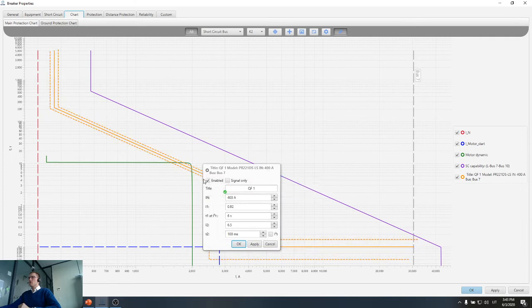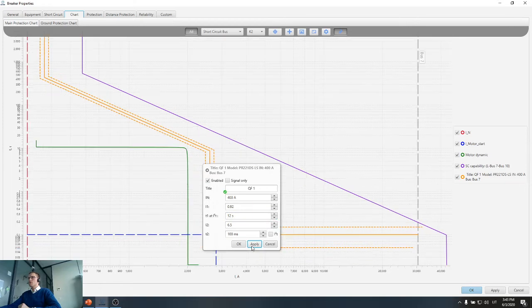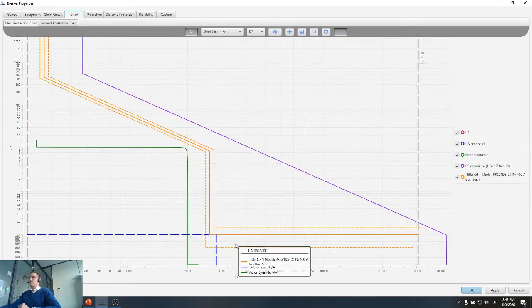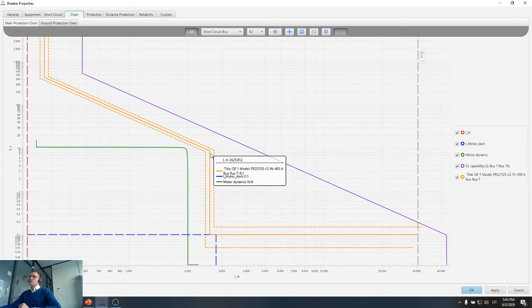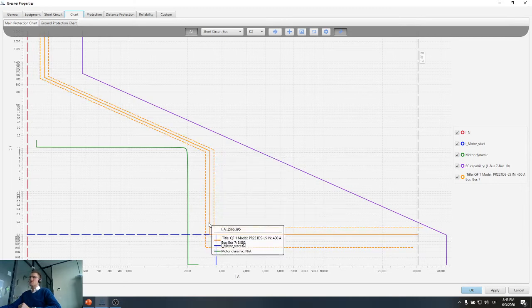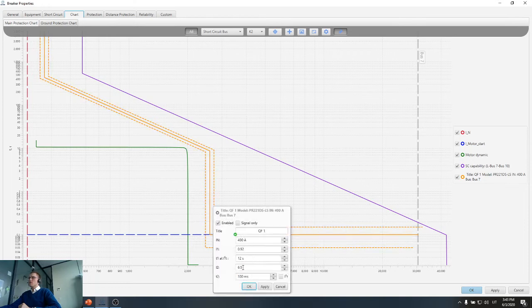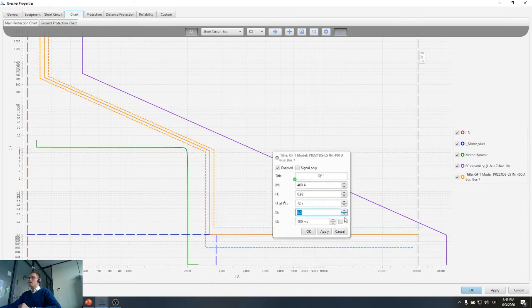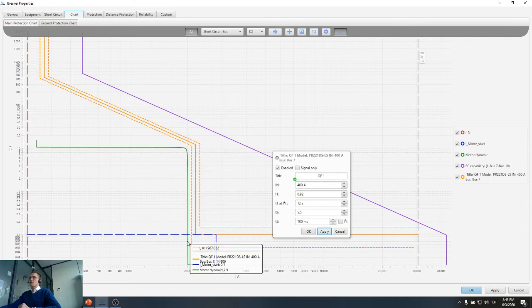Therefore I will double click on the line one more time, and I'll increase time as it was before, to 12 seconds. Now I also have to select a short time stage current setting. Basically I see that the current multiplier is 6.5, and if I reduce the current multiplier to 5.5, I will move my breaker characteristic closer to the motor starting curve. If I increase it, I will have a bigger safety margin.